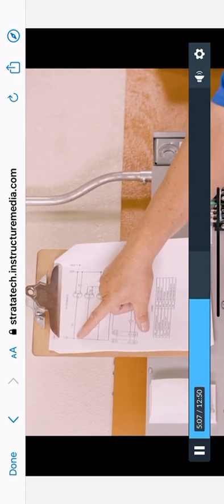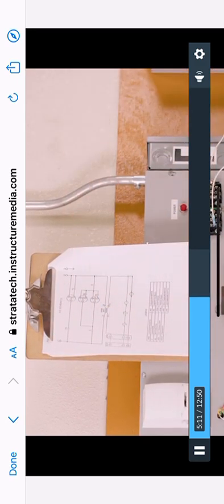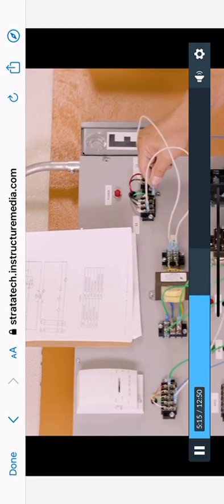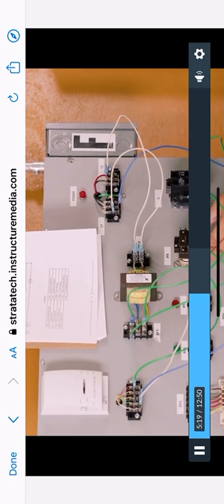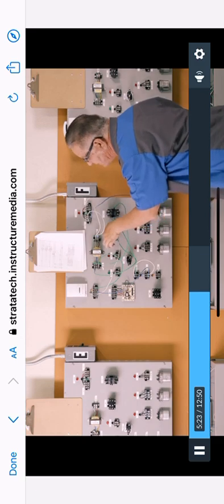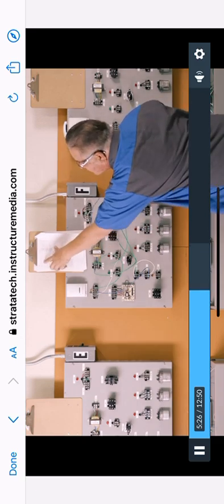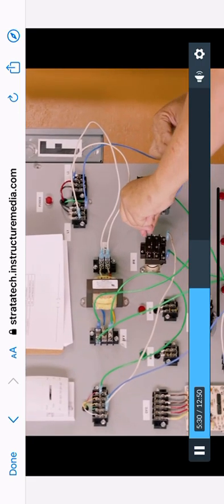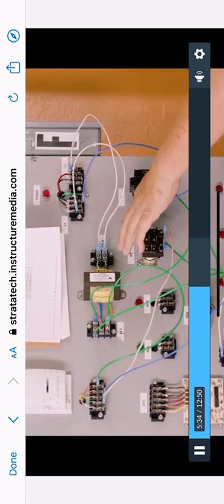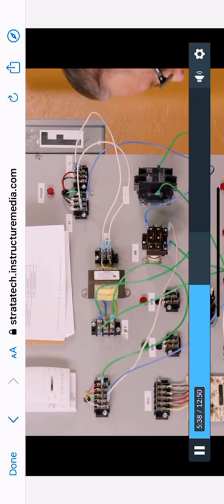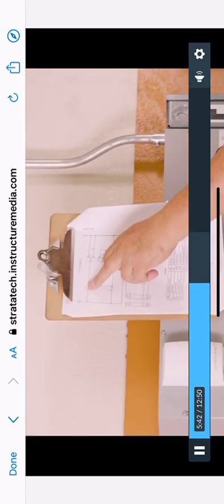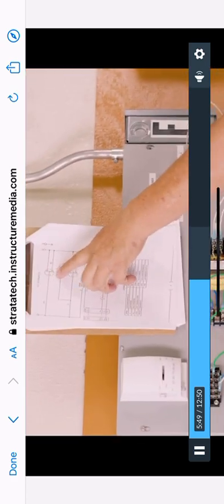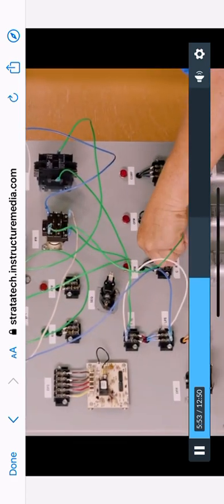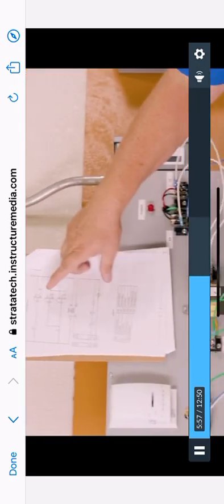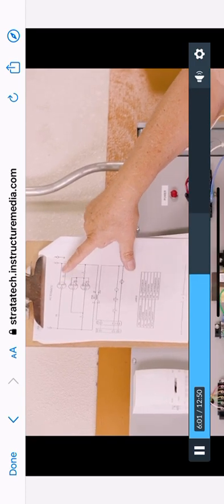Now I'm going to hook up my line 1 to my indoor fan relay. So I'm going to get a wire. This is high voltage. This is my coil on the indoor fan relay, which is what you see there. This up here is my switch, which is what you see there. So I'm on line 1 right now with this blue wire. I'm going to come in on one side of the switch. Your switches are across each other. So I'm going to come in here, and I'm going to come out here on the other side, which is what you see there. I just put this wire on. Now I'm going to come on the other side and go straight to my indoor fan motor. So I'm going to go here, and I'm going to my common of my indoor fan motor, which is right here. Okay, now I'm going to come off my run, off my motor, and I'm going to go straight to my line 2.